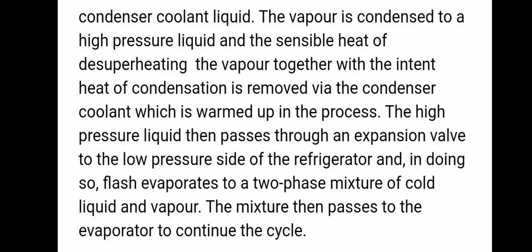The vapor is condensed to a high pressure liquid, and the sensible heat of desuperheating together with the latent heat of condensation is removed via the condenser coolant, which is warmed up in the process. The high pressure liquid then passes through the expansion valve to the low pressure side of the refrigerator. In doing so, it flash evaporates to a two-phase mixture of cold liquid and vapor. The mixture then passes to the evaporator to continue the cycle.